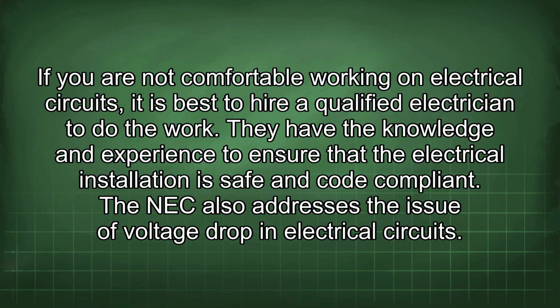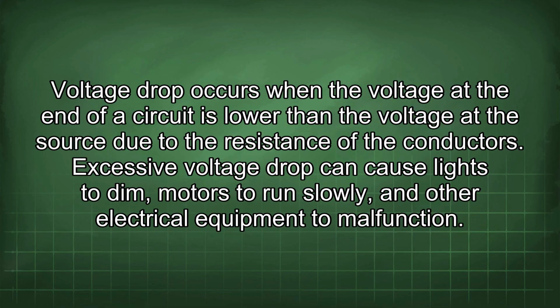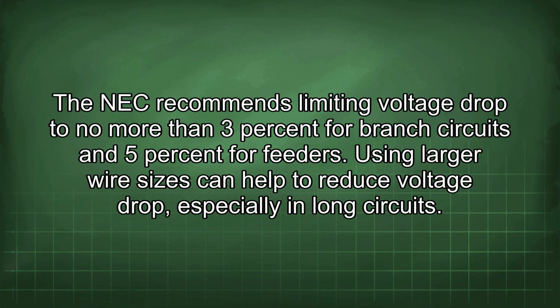They have the knowledge and experience to ensure that the electrical installation is safe and code compliant. The NEC also addresses the issue of voltage drop in electrical circuits. Voltage drop occurs when the voltage at the end of a circuit is lower than the voltage at the source due to the resistance of the conductors. Excessive voltage drop can cause lights to dim, motors to run slowly, and other electrical equipment to malfunction. The NEC recommends limiting voltage drop to no more than 3% for branch circuits and 5% for feeders.